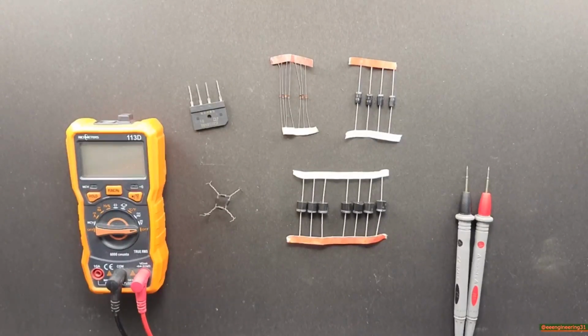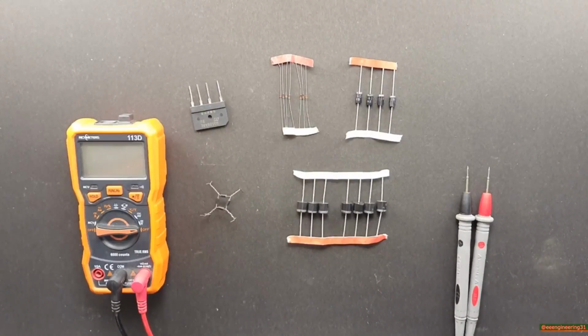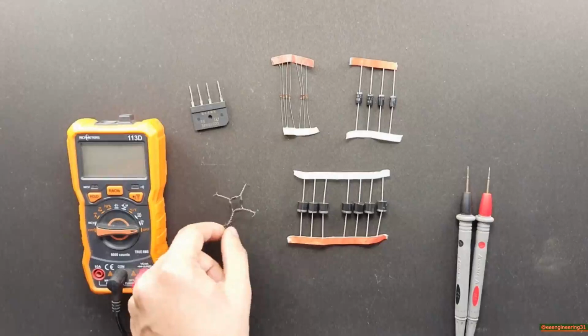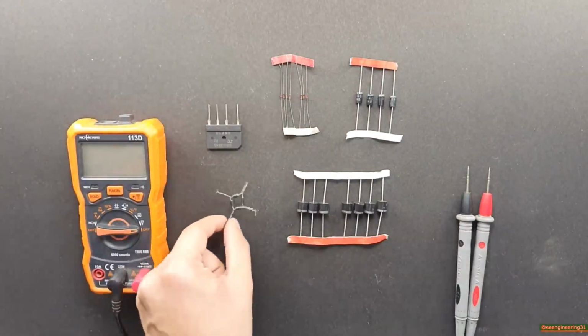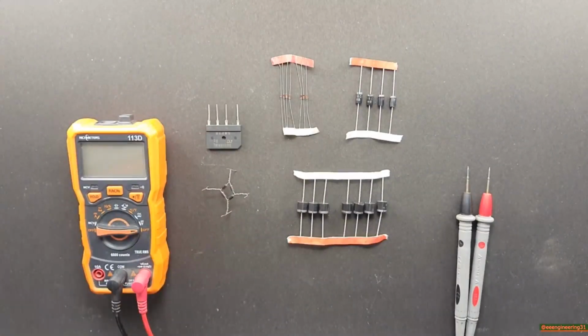In the sections of power supplies operating at the low frequency of the AC line, any rectifier is more than fast enough. The bridge or individual rectifiers at the AC side of the cord are not high-speed devices, nor are the rectifiers on the low voltage side of a linear supply. These kinds of rectifiers can be used to rectify the incoming AC into DC, and the frequency is 50 or 60 Hz.